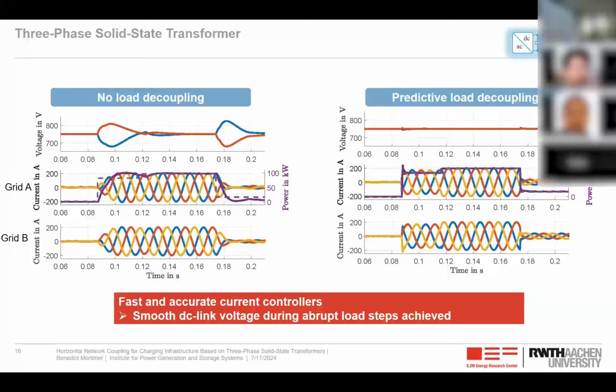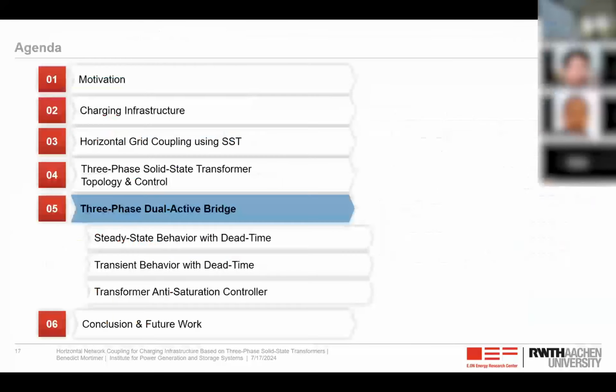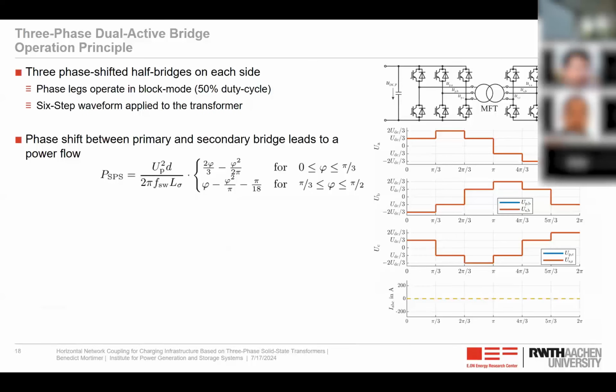However, as I said before, we need to take a look: can we actually assume that the behavior of the DAB can always be modeled as what we call the ideal behavior, because it's just a simple delay? So let's take a look at the three-phase dual active bridge. Typically we have 3 phase legs which operate in block mode with a 50% duty cycle. And so we get this 6-step waveform that is applied to the transformer.